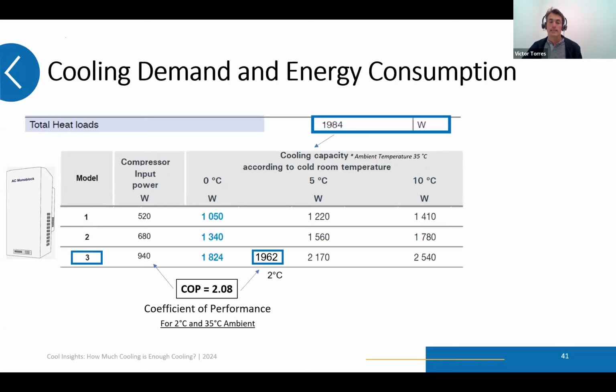Now we are selecting, based on that, the Model 3, which provides a cooling capacity of 1,900 watts at 2 degrees. This is what we need. If we divide this cooling capacity by the compressor input power, we get our COP, the coefficient of performance that we can expect for 2 degrees cold room temperature and 35 degrees ambient temperature. This COP gives us the relationship between thermal energy, cooling demand, and electrical power.